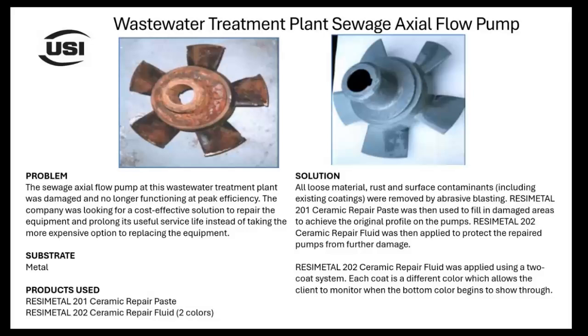Here we used our 201 paste again for repairs, and then the 202 as a protective coating on this flow pump. All the loose material, rust, and surface contaminants, including the existing coatings, were removed by abrasive blasting. Then Resimetal 201 ceramic repair paste was used to fill in the damaged area to achieve the original profile on the pumps. The Resimetal 202 ceramic repair fluid was then applied to protect the repaired pumps from further damage.